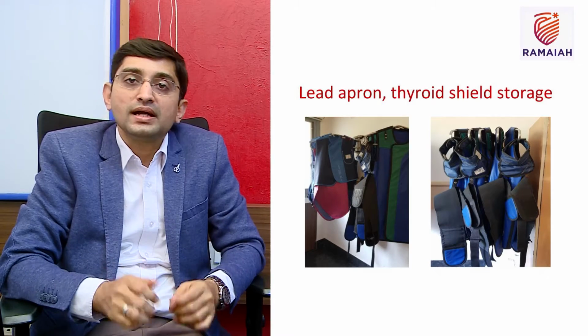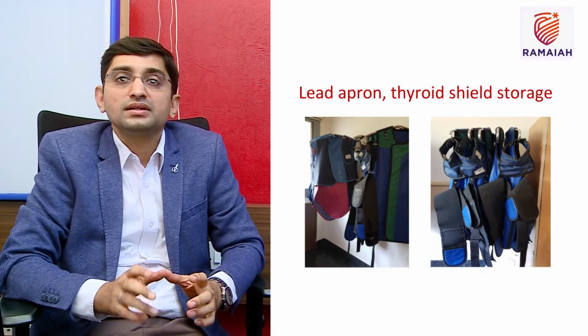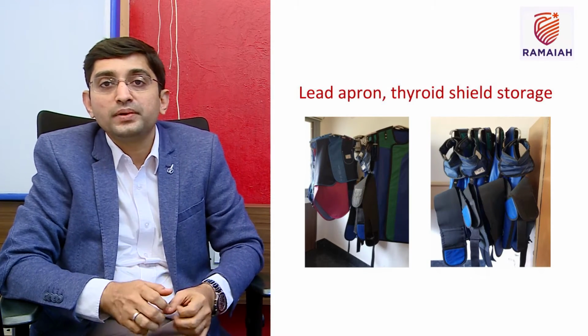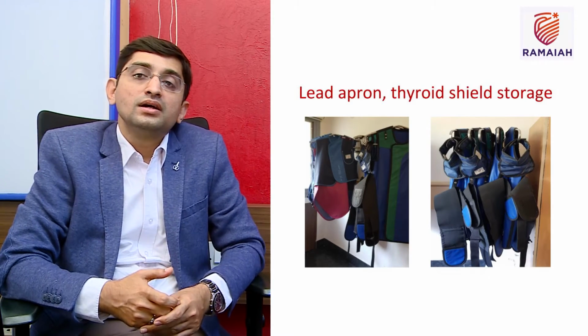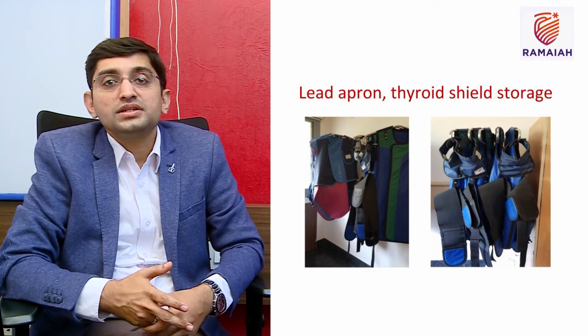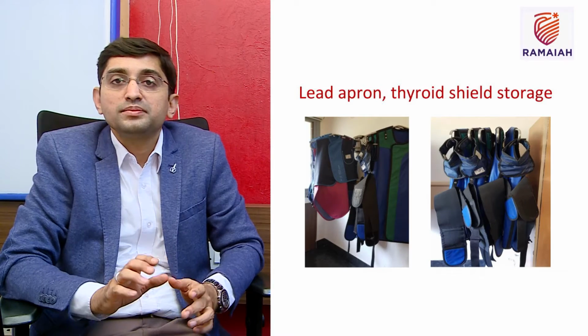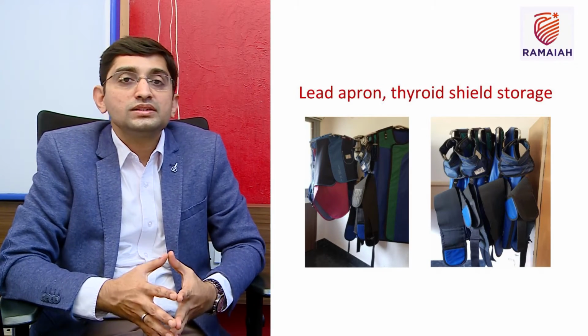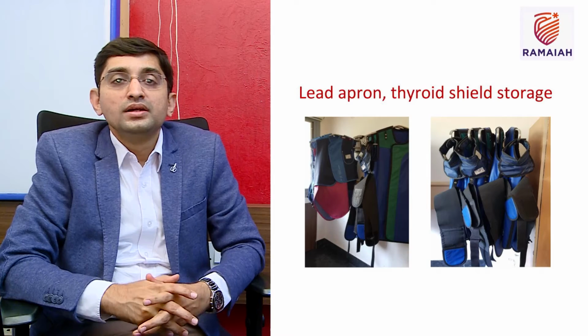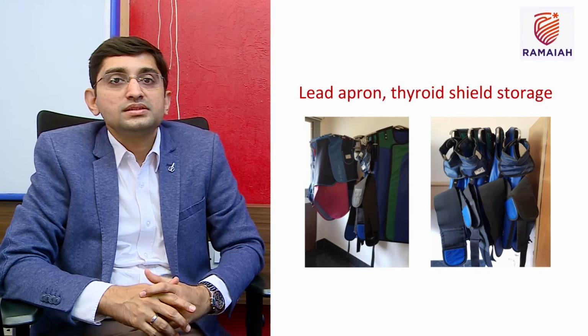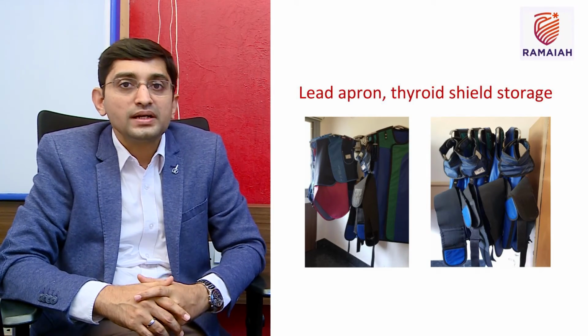They should be stored standing on different stands, so that the lead aprons or lead shields don't break and the efficacy of the lead protection is not lost. We should always check the efficacy of the lead apron by looking at the radiation hazard at least once in 6 months or once in a year. So this concludes the first part, which is cleaning and disinfection of the endoscope and its accessories.